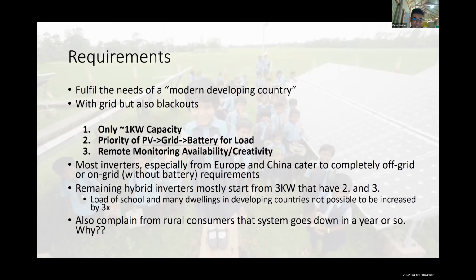Most inverters, especially from China, cater to either completely off-grid or on-grid without batteries, since that fits the situation in countries where grid electricity is rare. However, Bangladesh is 100% electrified, so we need hybrid inverters that can use the grid, but also a battery and the PV. This puts a fair bit of pressure on the inverter, and because of the complexity, most inverters start from 3 kilowatts, which is 3 times what we need.